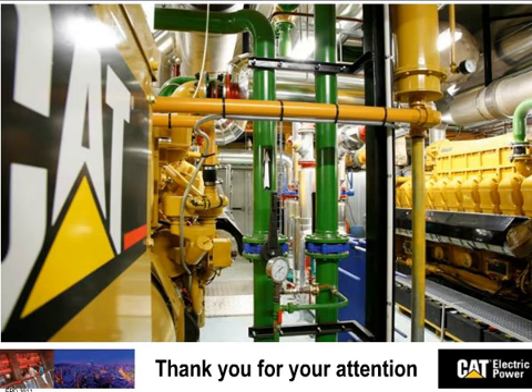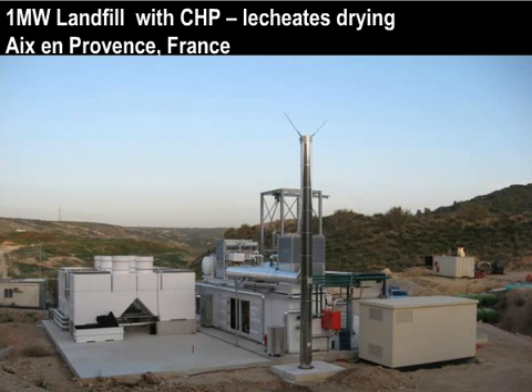Yes, if you have a chance near your landfill to have a heat consumer, that's fantastic, because you can use the heat produced by the landfill power plant or the biogas power plant and send it to the local customer. Heat can be stored but cannot be easily transported, so you need to have a heat consumer nearby. Since you have contaminants in these gases, the only thing you need to pay attention to is how low you cool down the exhaust gas and what stainless steel is in the exhaust gas heat exchanger, but this is quite easy to solve.